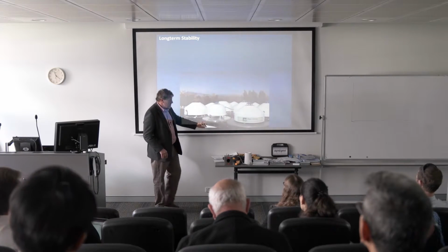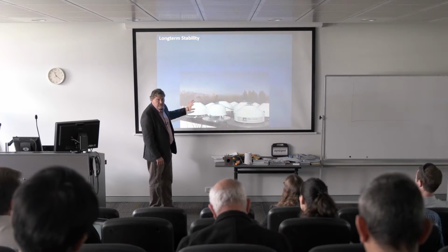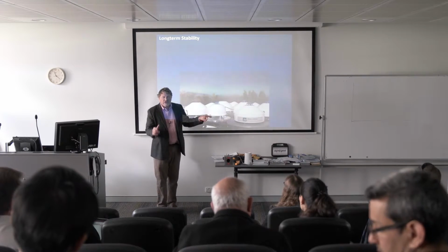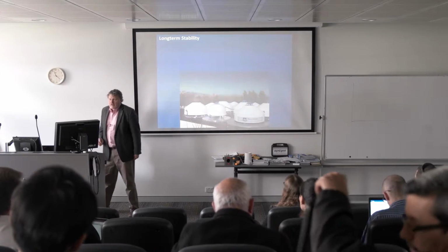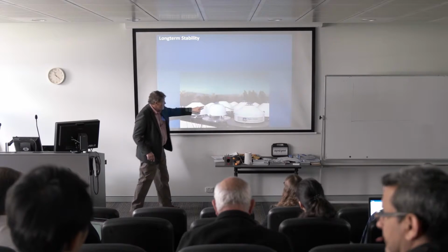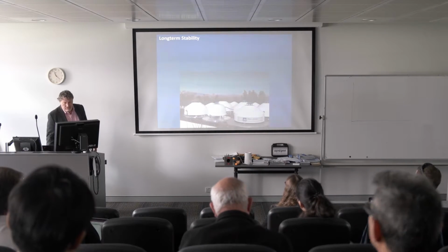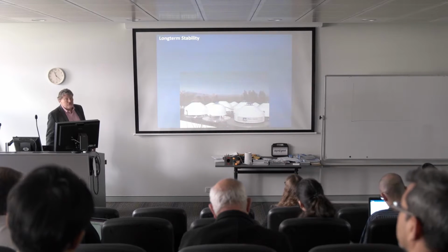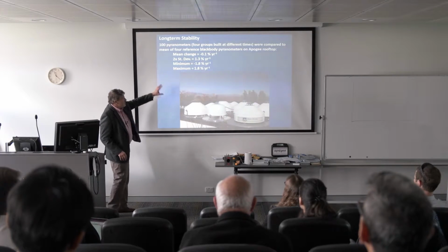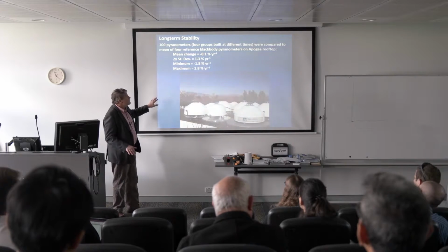Now, Kipp & Zonen sells very expensive high-end black bodies. This is on the roof of our building in Logan, Utah. Multiple replicate high-end instruments to get a very accurate reference point. And you can see there's 2 glass domes inside of these to make a primary standard instrument. So here's data. Now we don't show the 100 pyranometers next to these, but it's a big table of checking them.